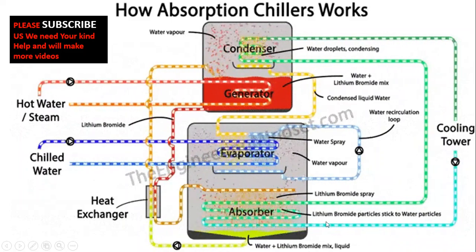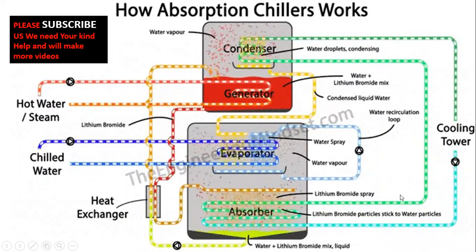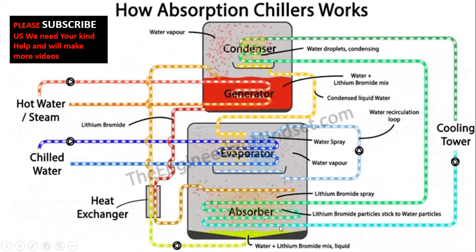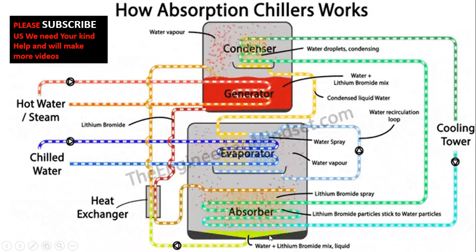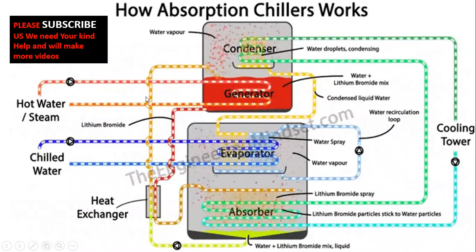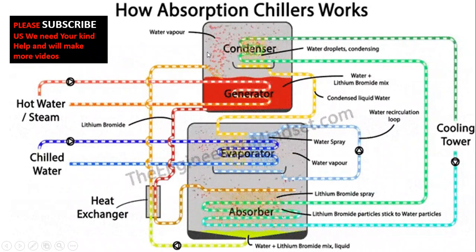A cooling coil from the cooling tower is present in the absorber. The water and lithium bromide mixture condenses back into liquid form due to this cooling. This combined solution is then pumped back to the generator, completing the full cycle of the absorption chiller.